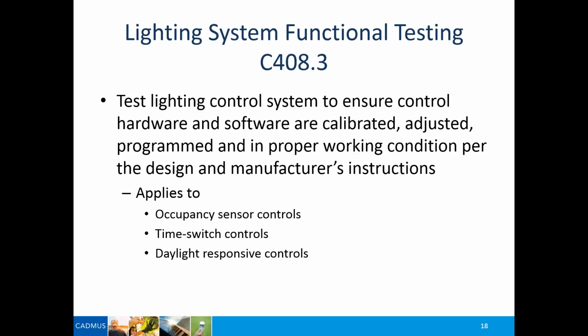And this is going to be a key thing to making sure that we're actually getting the energy savings that we need out of these lighting controls, because we've seen really bad examples of lighting control systems put in spaces that don't function properly, and there's complaints by the occupants. The lights don't dim when they're supposed to, or they dim when they're not supposed to, and that type of thing. They're just not set up right. And so this, again, is a brand new requirement that requires you to actually test these systems to make sure they are operating as designed.